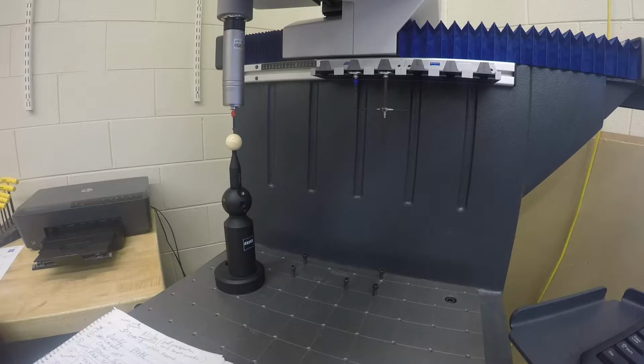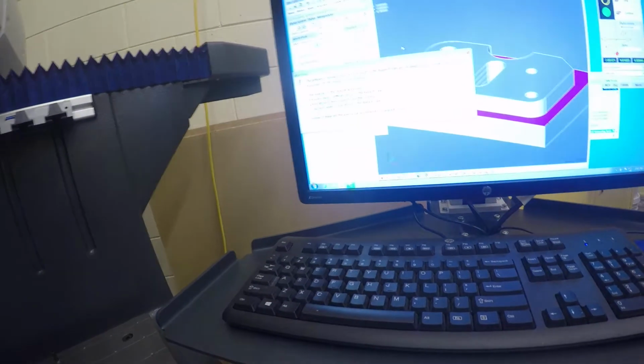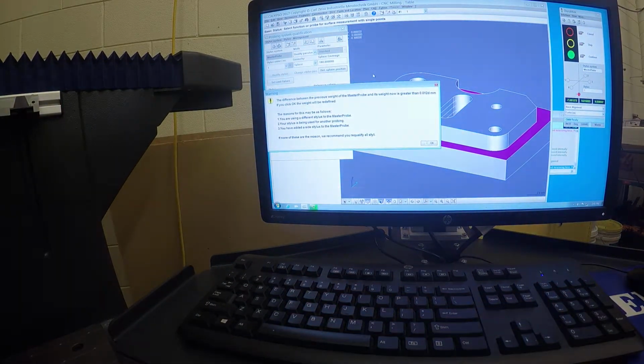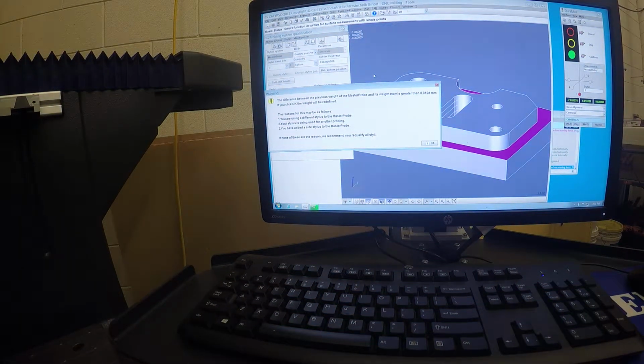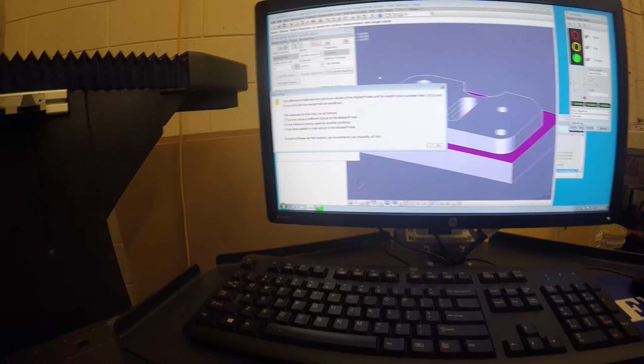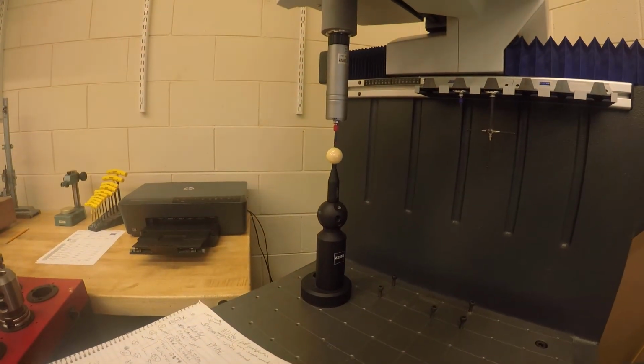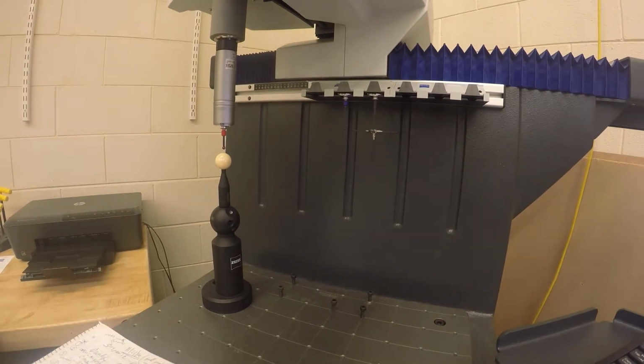Difference between the previous weight of the master probe and its weight now is greater than blah, blah. The weight will be redefined. I'm looking at this error message. So the reasons for this may be you're using a different master probe, the stylus is being used for another master probe, or you have added a side stylus. None of these reasons, we recommend to requalify the styli. So for the purpose of this video and the process, I'm going to continue.